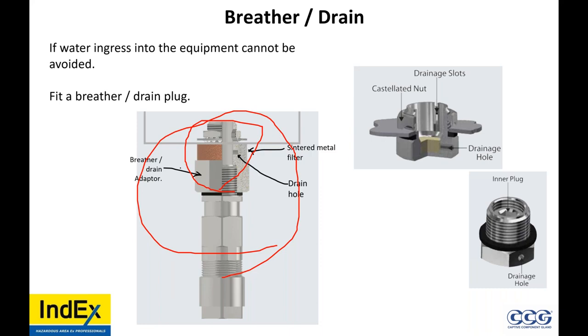Correct. So there were small things as well. You commented on thread galling on MPT threads. That will only happen if the cable gland is the same material as the enclosure. However, I fully agree with your comment about using a thread lubricant, a grease, when you install these. If you don't, you cannot guarantee your IP rating.